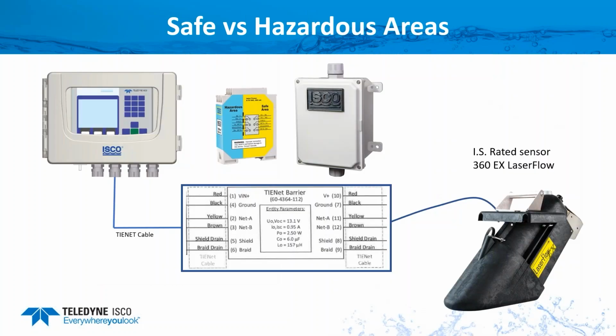Now let's take a closer look at that IS barrier. What we have here is the laser flow sensor, which is classified, connects to a barrier, which is clearly marked with the safe zone and hazardous. So make sure you connect it the right way. The sensor would connect to the hazardous side. It's clearly marked as to where all the wires land.